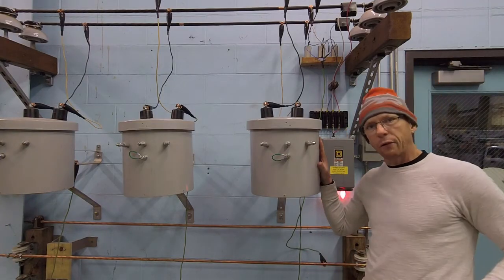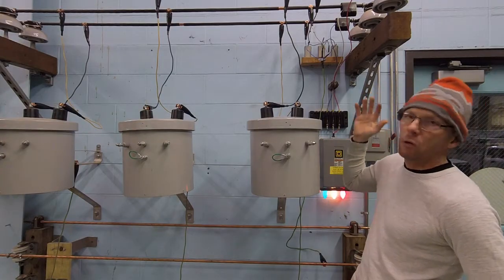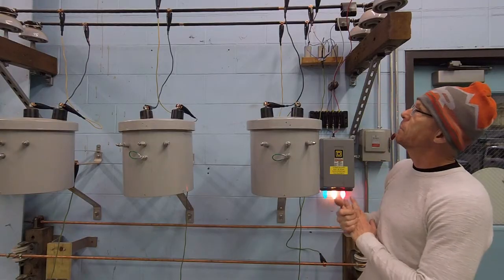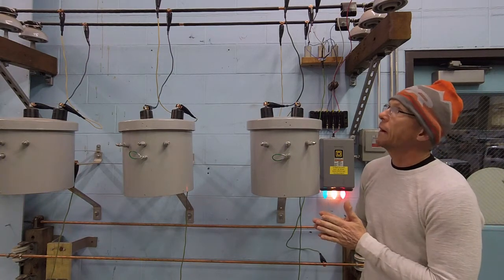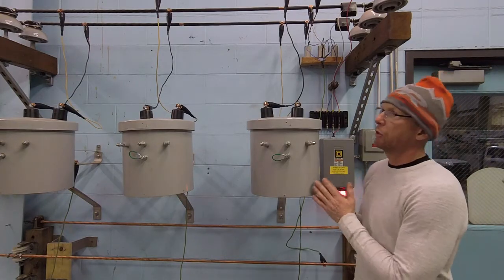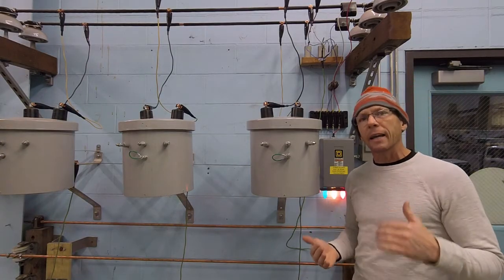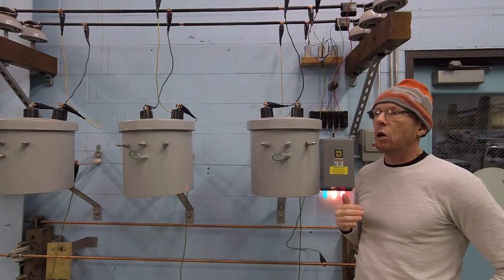The issue I had with trying to create this circuit in the lab was that although I do have an inductive component within the transformers to use to fill that requirement, I don't have any capacitive components because this is basically an overhead circuit, it's modeled after an overhead transformer bank, and the bus bars up here do not hold any inherent capacitance within them. Another issue that was affecting the recreation of this phenomenon in the lab is that the voltages I'm working with in here are not really sufficiently high enough such that the capacitive reactance involved with the source of feed can come into play effectively.